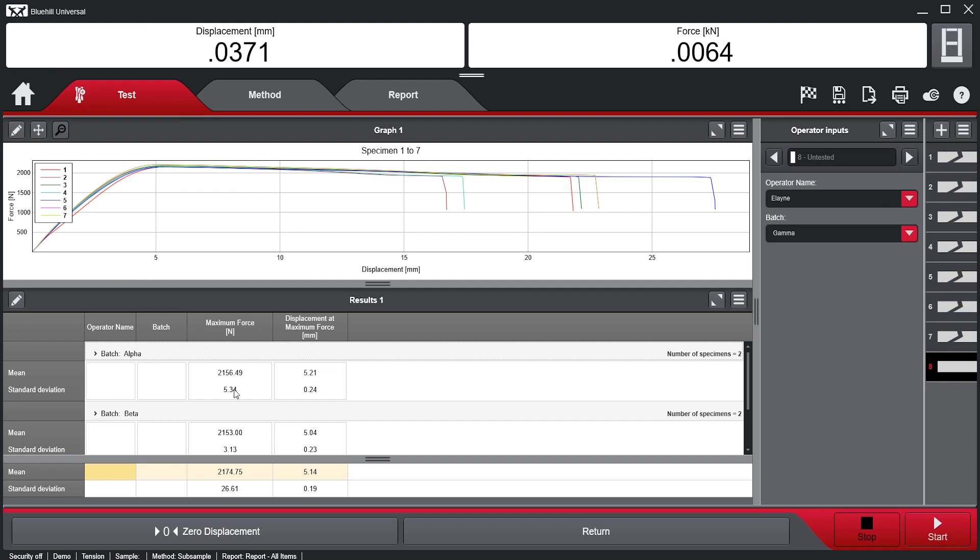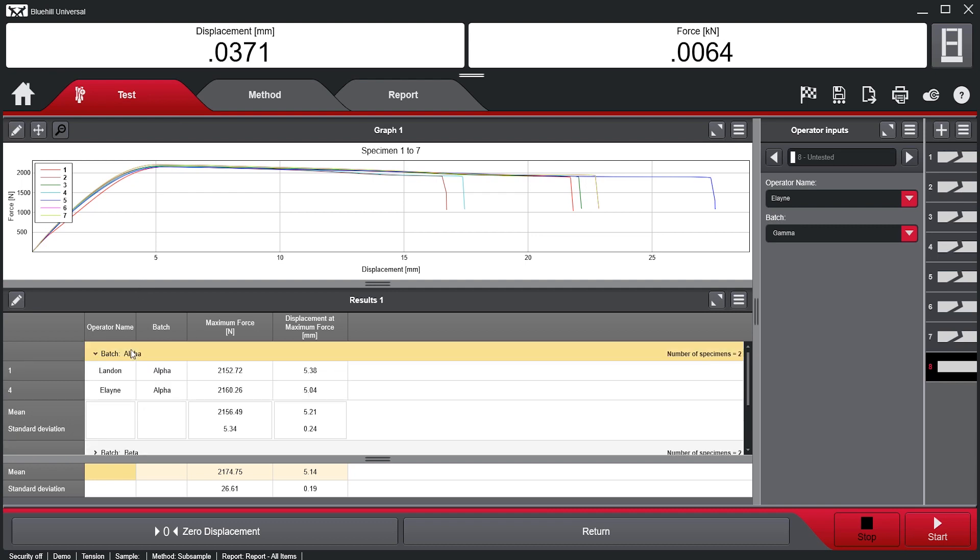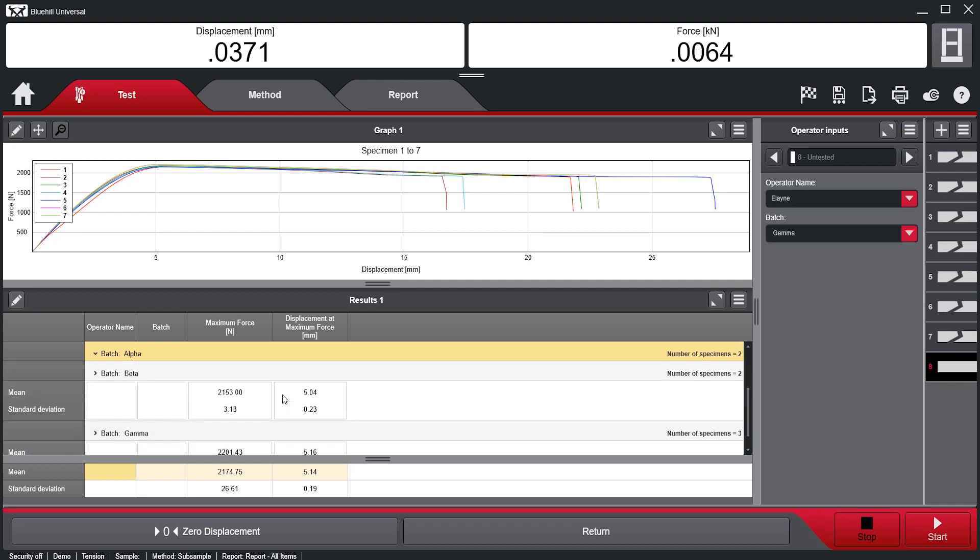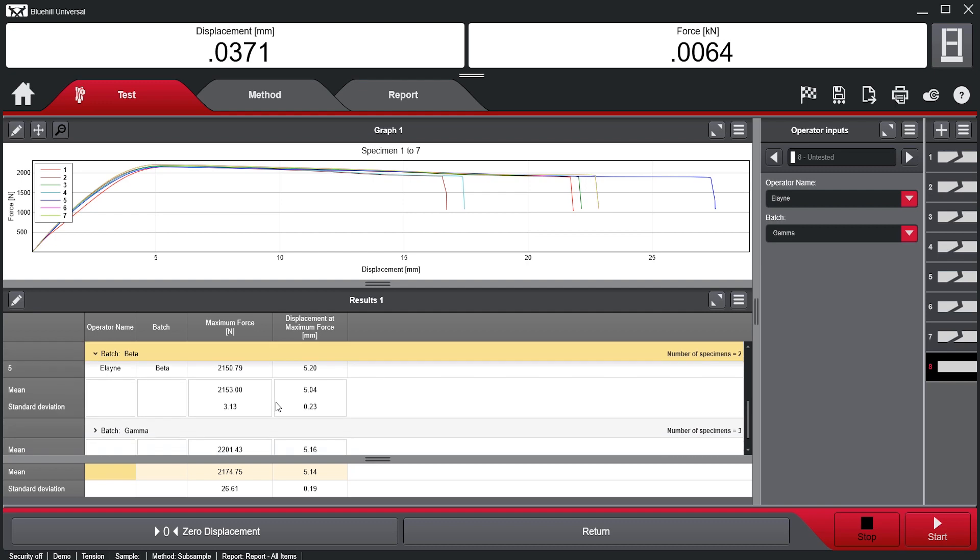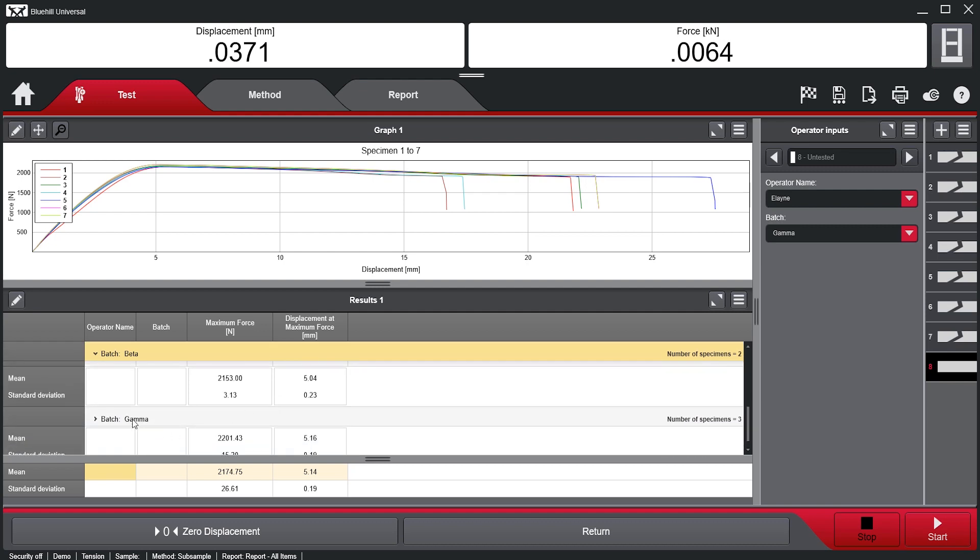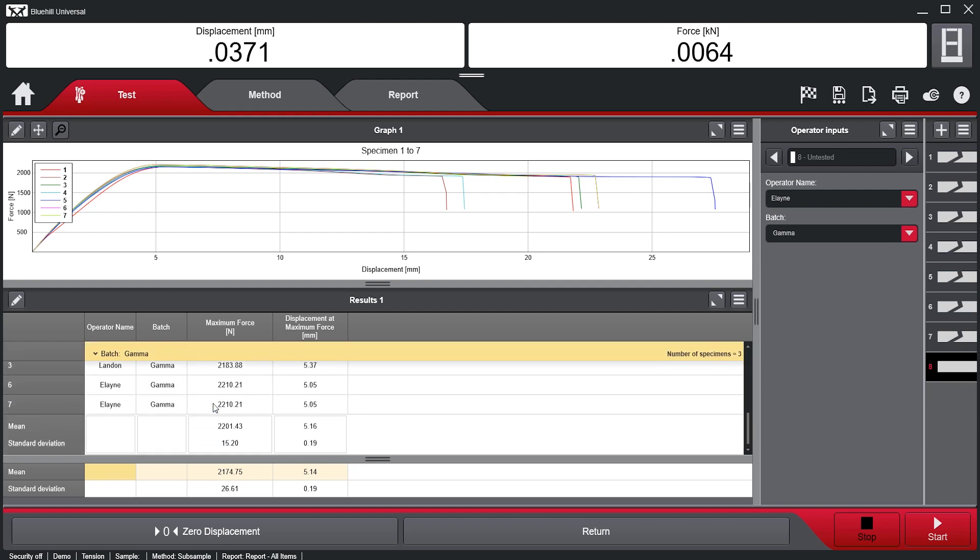Open the Task menu and enable Show Group Statistics. Each subsample now has its own set of statistics, allowing the user to better analyze specimen variations and make more meaningful insights from their testing. The Group All Default can be minimized to keep the results table easy to read.